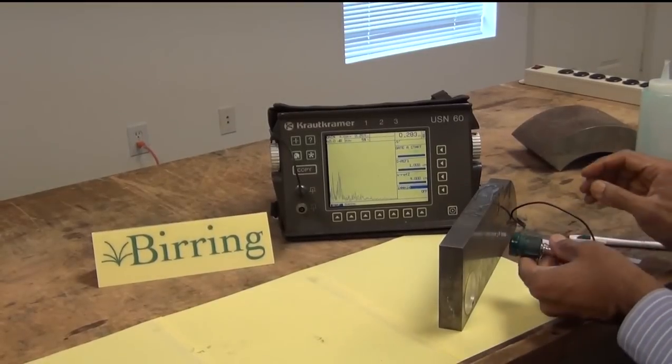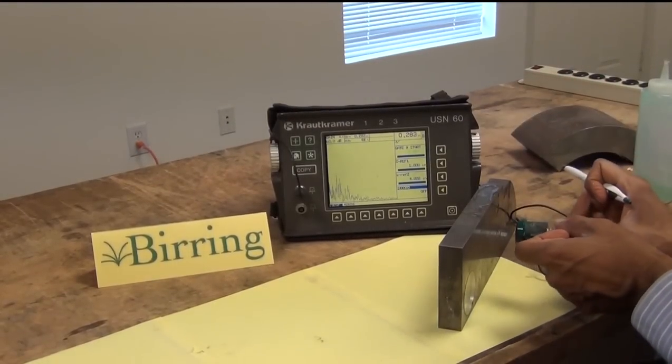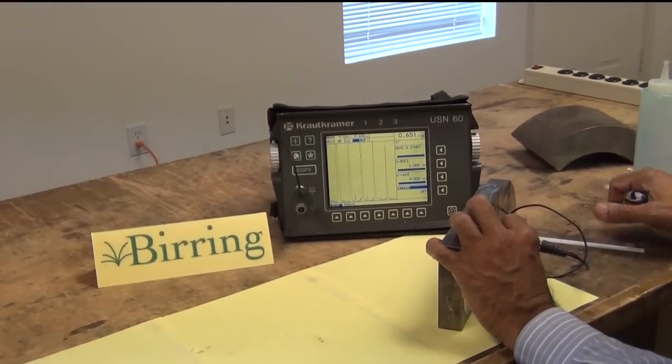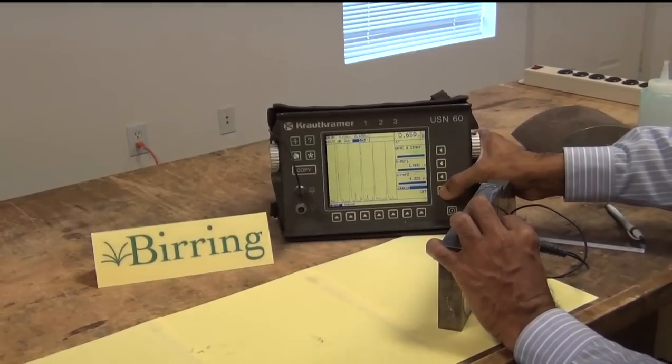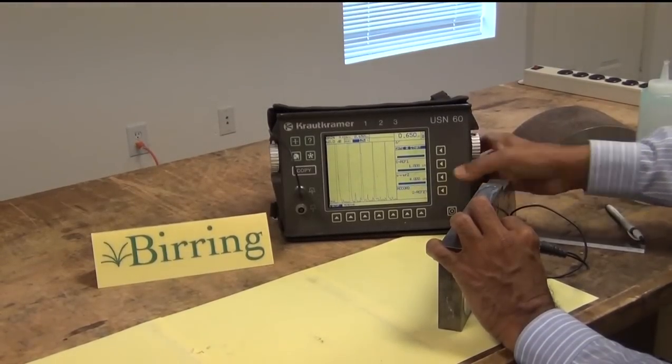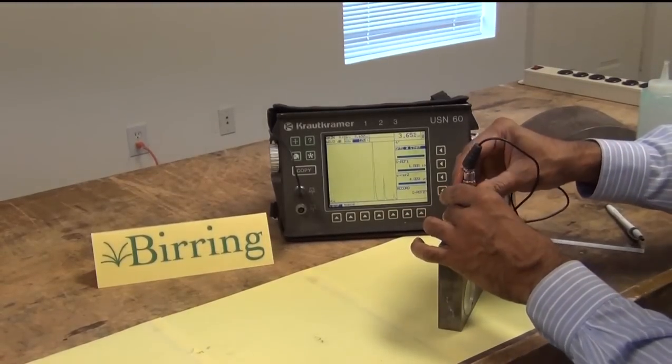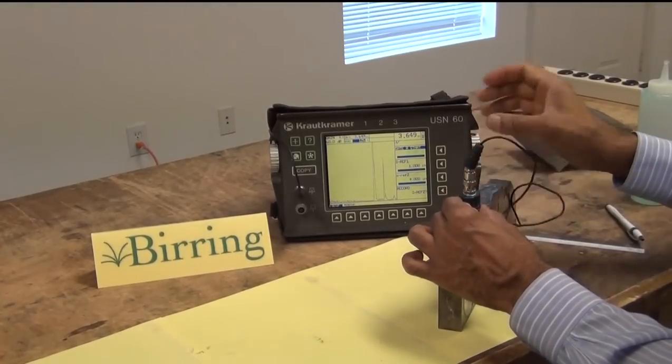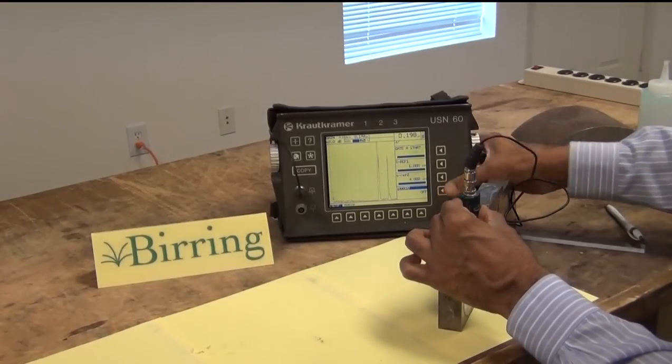We are ready to do the AutoCal. The two steps chosen are 1 inch and 4 inch. I will first put it on the 1 inch side and here is the signal from the 1 inch. We will start the recording process. Record S reference 1. Then it's asking for S reference 2 which would be here and that's 4 inches, and I will enter S reference 2 as 4 inches and we are done.